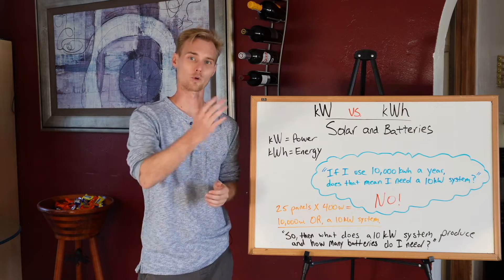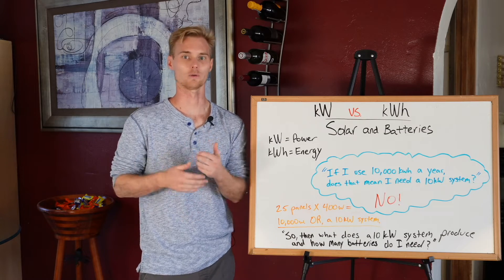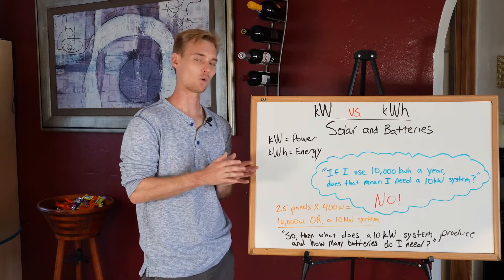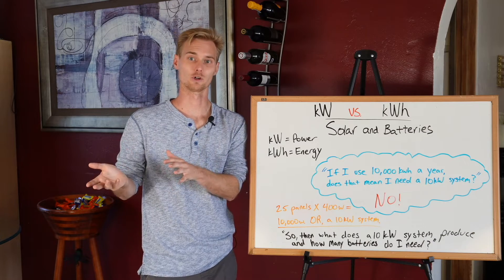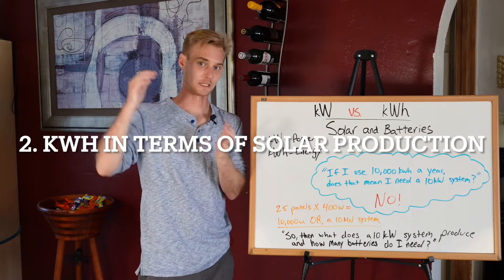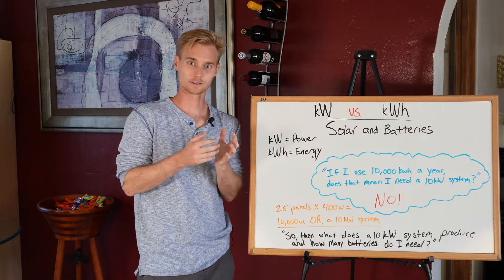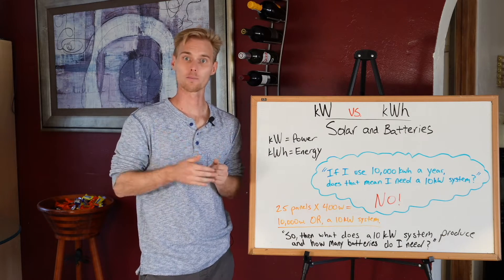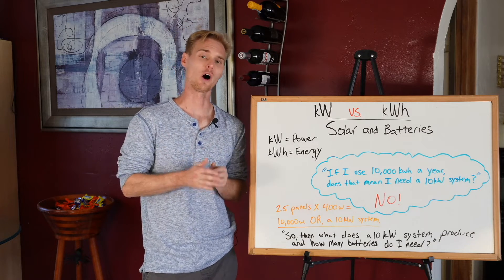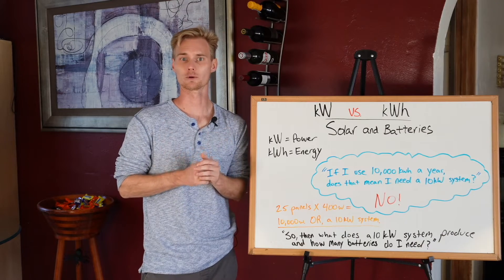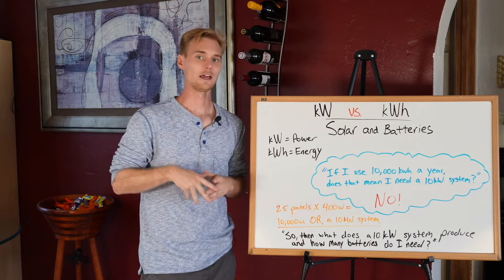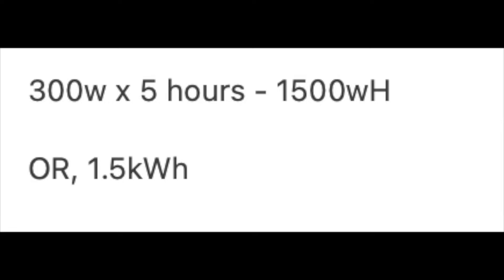It depends on where you are — the more north you are, the less you're going to produce. There are many factors, including the azimuth and the direction the panel is facing. Theoretically, let's say a 400 watt panel produces around 300 watts in the real world. If that panel is getting hit by the sun and producing 300 watts for one hour, at the end of that hour you'd have produced 300 watt hours, or 0.3 kilowatt hours. On a daily basis, one panel usually produces somewhere in the range of 1.5 to 2.5 kilowatt hours — if it produces 300 watts for five hours, that's 1,500 watts or 1.5 kilowatt hours.